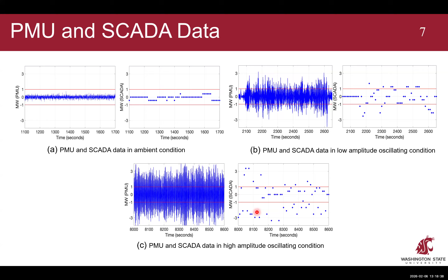And one thing that we want to caution in using SCADA for this type of oscillation analysis is that some of the utilities include or implement low pass filters or slow smoothing filters in the SCADA before it comes to or after it comes to the control center. And unfortunately, something like that will kill this information that we are looking for.